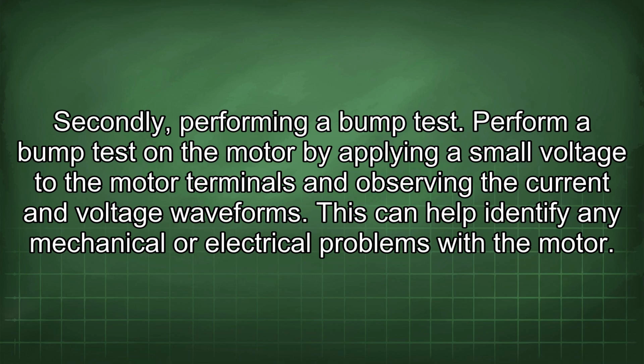Secondly, performing a bump test. Perform a bump test on the motor by applying a small voltage to the motor terminals and observing the current and voltage waveforms. This can help identify any mechanical or electrical problems with the motor.